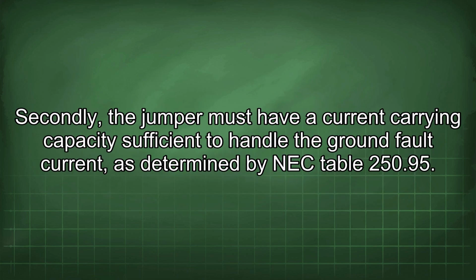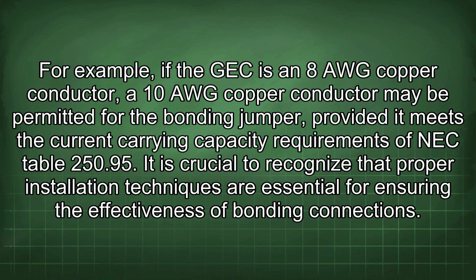Secondly, the jumper must have a current carrying capacity sufficient to handle the ground fault current, as determined by NEC Table 250.95. For example, if the GEC is an 8 AWG copper conductor, a 10 AWG copper conductor may be permitted for the bonding jumper, provided it meets the current carrying capacity requirements of NEC Table 250.95.